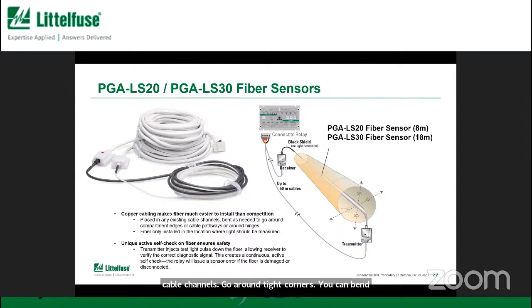In some cases, if you have large equipment and it's split in sections, you could even cut the copper cabling and have it connect with terminals. It makes it very flexible. So this cabling does make it very easy to use. The fiber itself also has a very unique self-check that I'll talk about in a moment to make sure that the fiber is not cut or damaged as well.